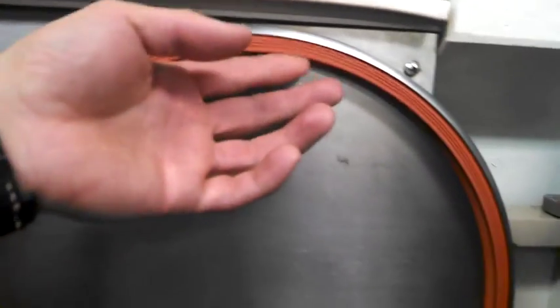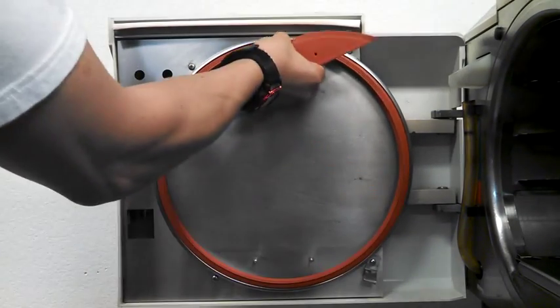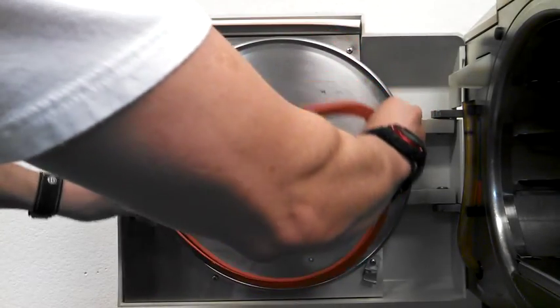A couple of ways you can tell if your gasket needs replacing is if it's loose like the gasket that's here right now on the door, if you see an excessive amount of water under the unit, or if you see an excessive amount of steam coming out the sides of the door.